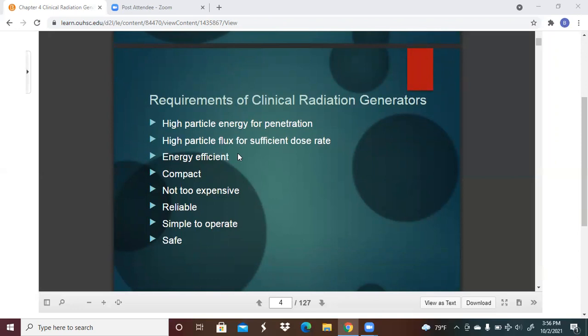So what are the requirements here for clinical radiation generators? Well, we're going to need high particle energy in order to get the particle to have enough energy to penetrate through the patient. We're going to need a lot of them, and that's where the high particle flux comes from. In other words, we're going to have a number of particles going through a particular area. So in order for us to be able to generate a sufficient dose rate, that's what we're going to need.